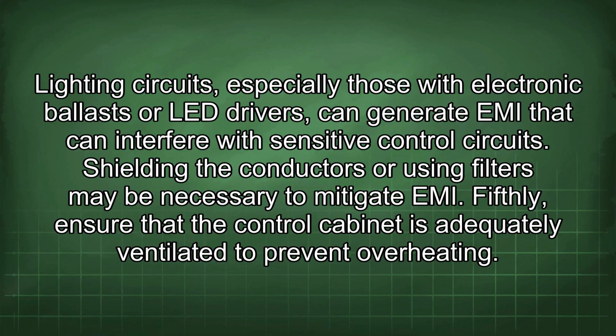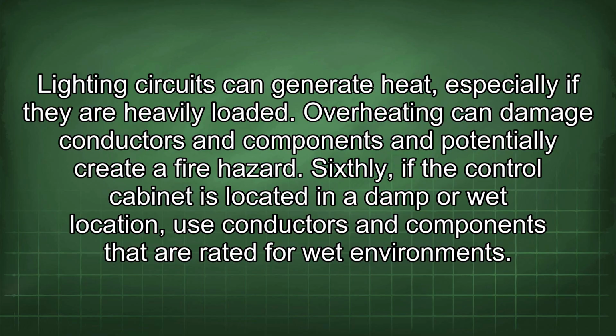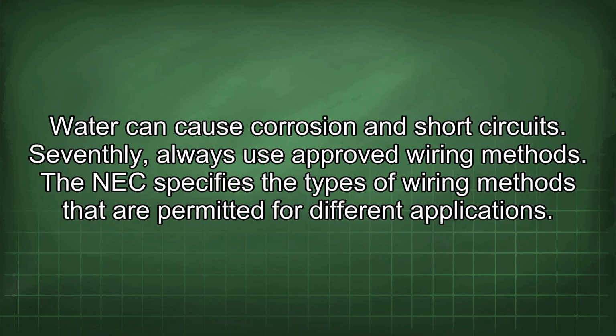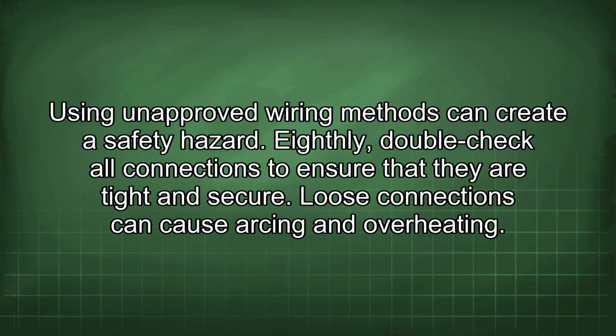Fifthly, ensure that the control cabinet is adequately ventilated to prevent overheating. Lighting circuits can generate heat, especially if they are heavily loaded. Overheating can damage conductors and components and potentially create a fire hazard. Sixthly, if the control cabinet is located in a damp or wet location, use conductors and components that are rated for wet environments. Water can cause corrosion and short circuits. Seventhly, always use approved wiring methods. The NEC specifies the types of wiring methods that are permitted for different applications. Using unapproved wiring methods can create a safety hazard. Eighthly, double-check all connections to ensure that they are tight and secure. Loose connections can cause arcing and overheating.